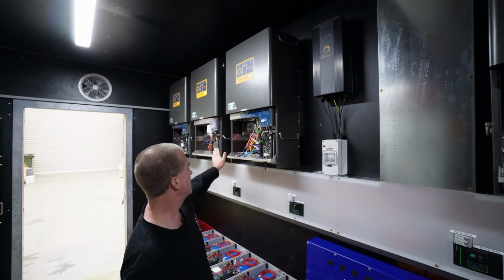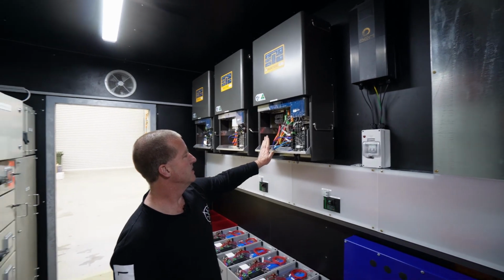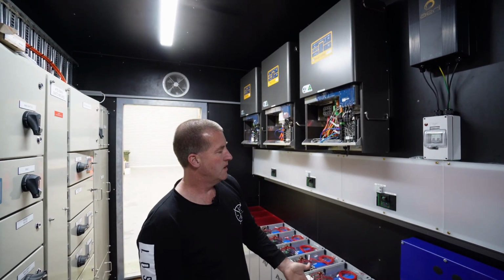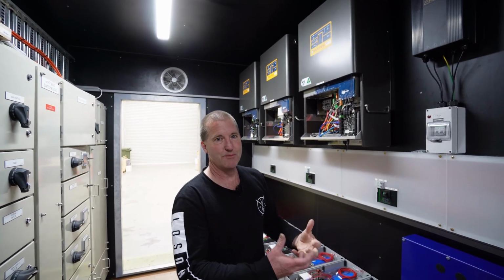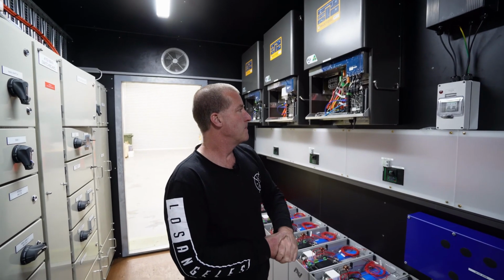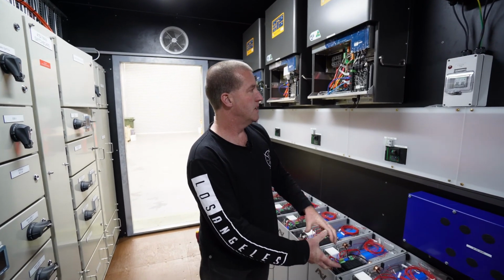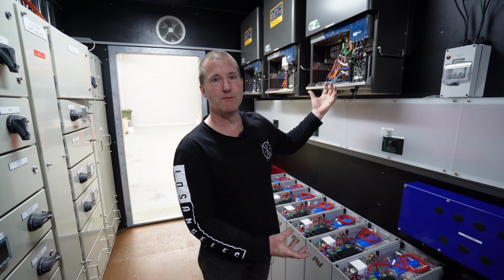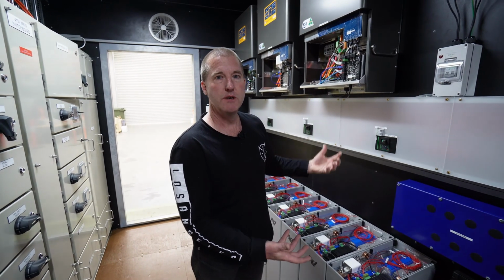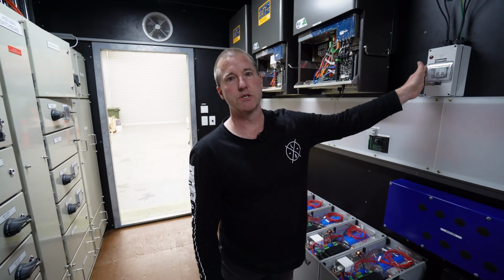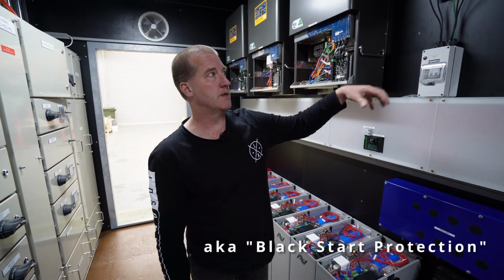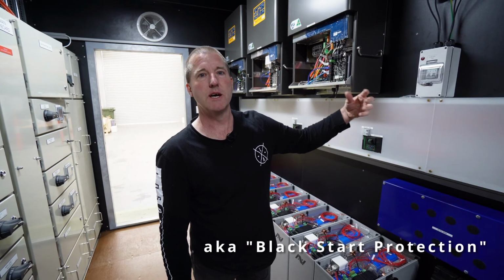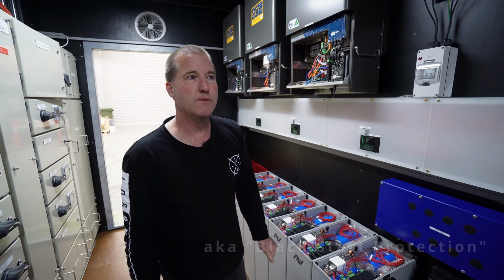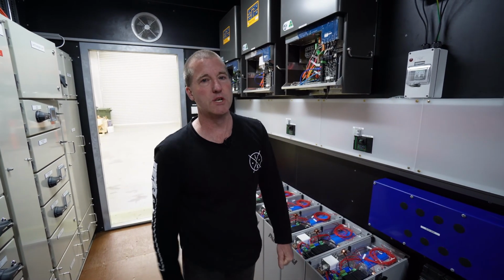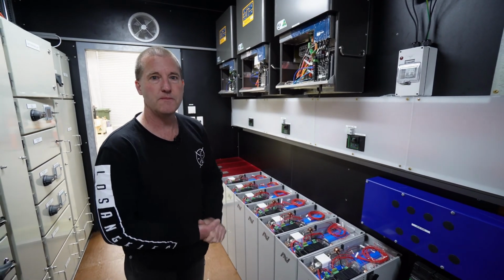We can use a generator coming into these inverters that can produce DC and charge the batteries. But one problem a lot of people know about is that when you have a flat battery, sometimes an inverter won't actually come on because it needs to see power to come alive. That's why having a DC charge controller is a good idea, because you can always come alive with what we call a black start, where there's only sunshine available. Or alternatively, we can use a small generator through the power supplies to bring the batteries up.